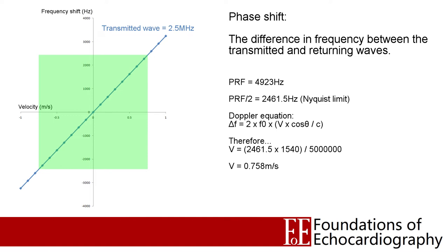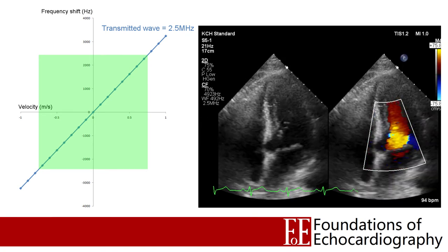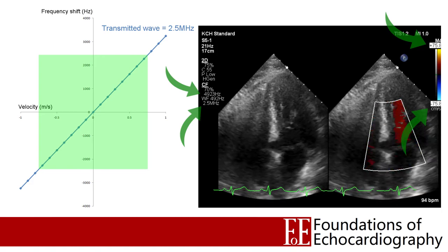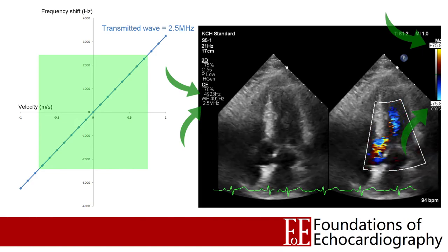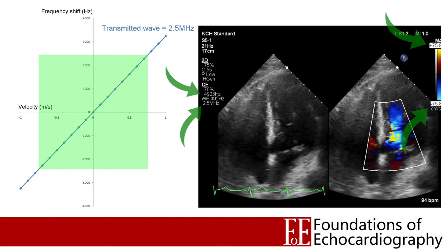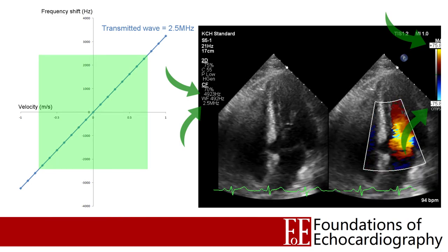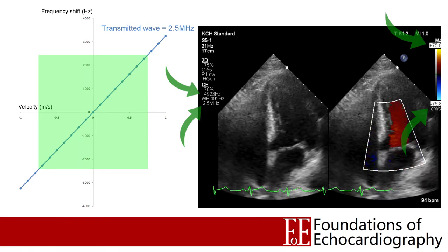Any velocity up to 75.8 cm per second is going to produce a frequency shift within our detectable range, but any velocity in excess of this value will produce a frequency shift we can't accurately describe. On the clip you can see the colour scale on the far right of the image, and the ultrasound software is telling you that with the settings as they are, the maximum velocity that can be displayed is the 75.8 cm per second that we anticipated. When the observed velocity exceeds the upper bounds of the scale, this is when aliasing occurs.